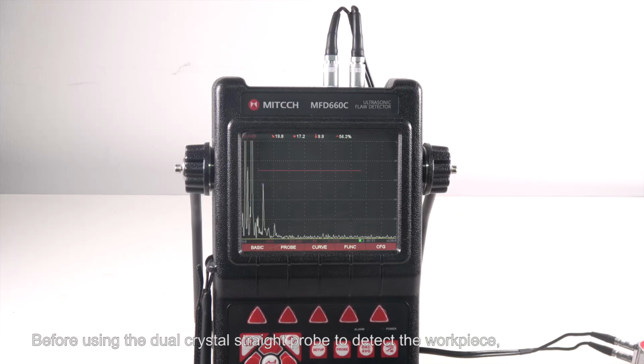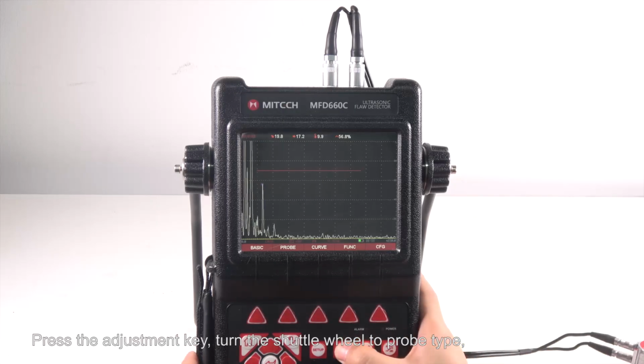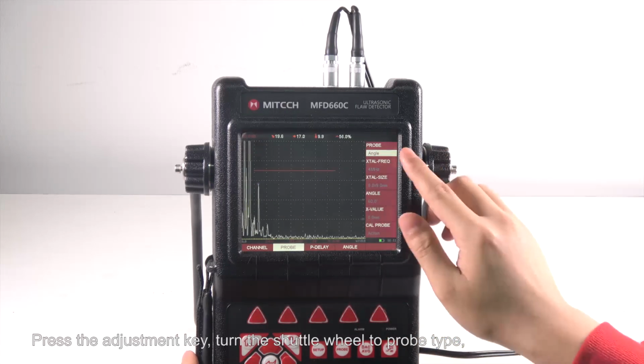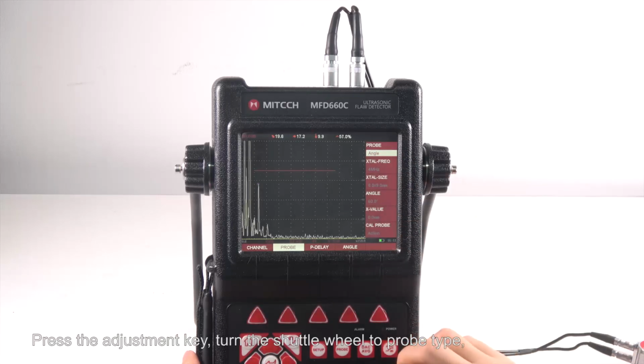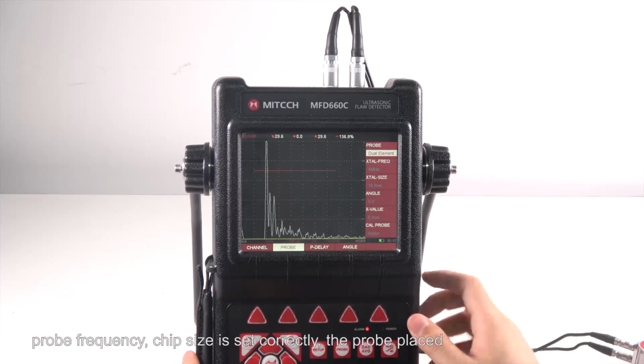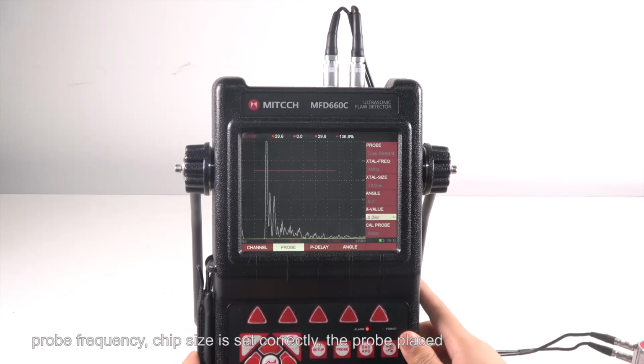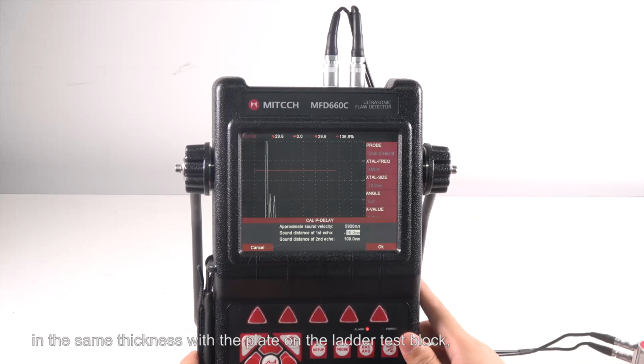Before using the dual crystal straight probe to detect the workpiece, we need to adjust the probe zero adjustment and sensitivity. Proceed as follows. Press the adjustment key and turn the wheel to probe type, probe frequency, and chip size, and set them correctly. The probe is placed on the step of the ladder test block with the same thickness as the plate.